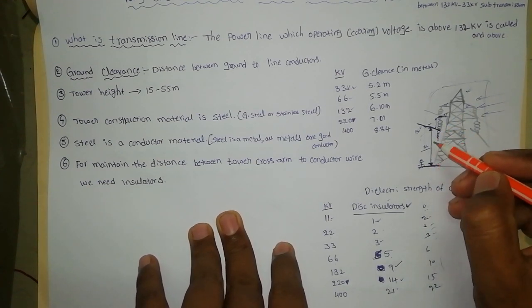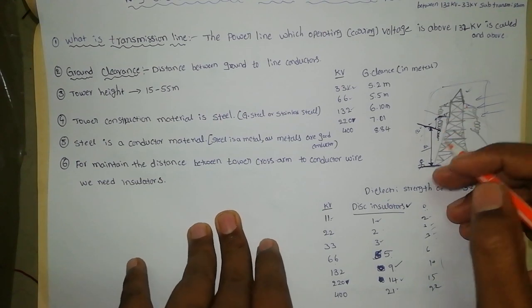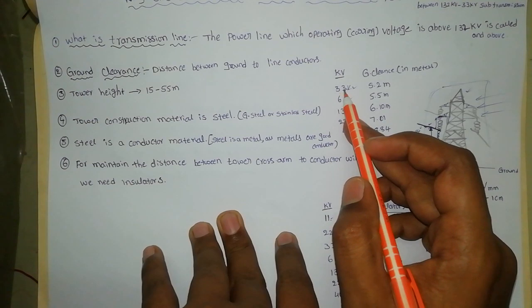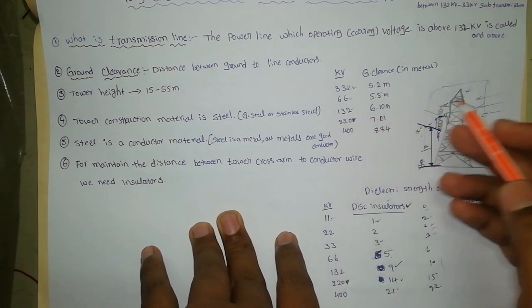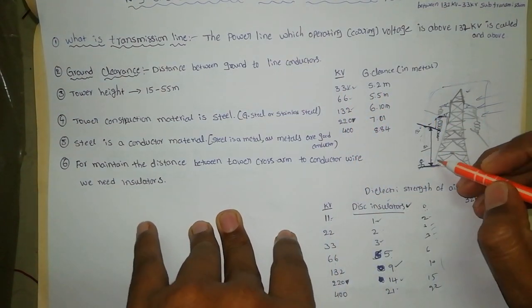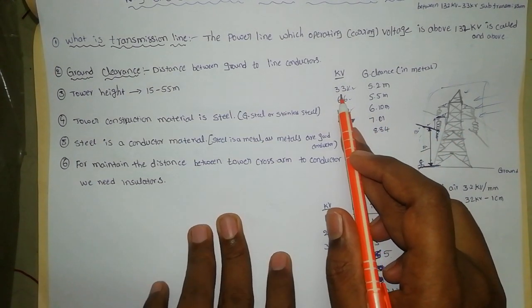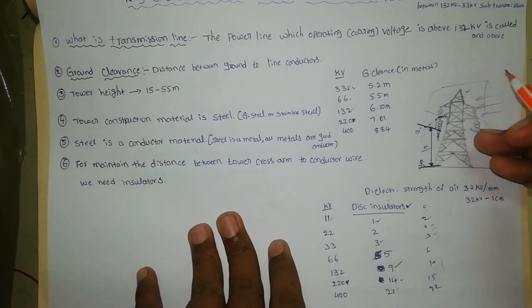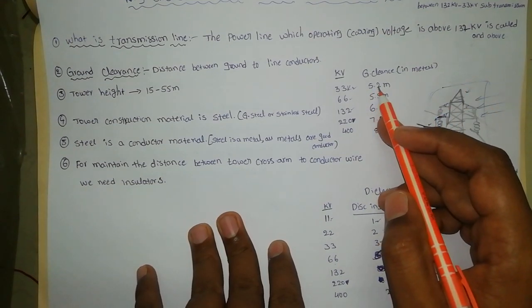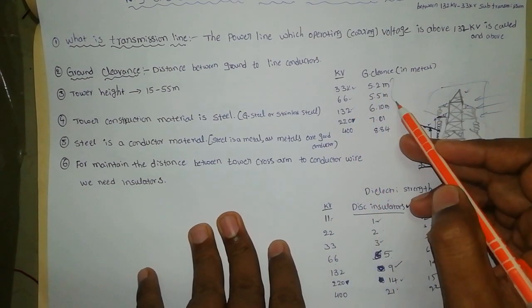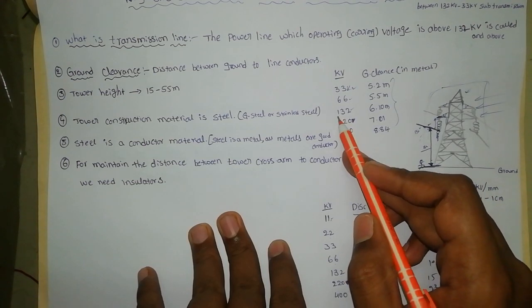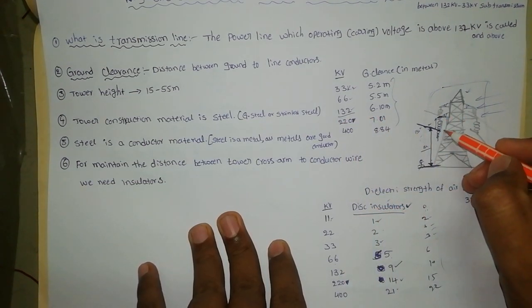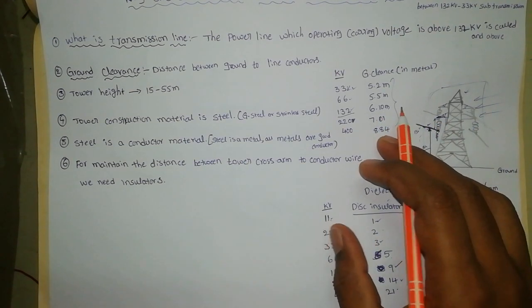The safe distance for 33 kV is 5.2 meters height. If your operating voltage is 33 kV, the ground clearance must be above 5.2 meters. If the operating voltage is 132 kV, the tower height must be above 6.10 meters.